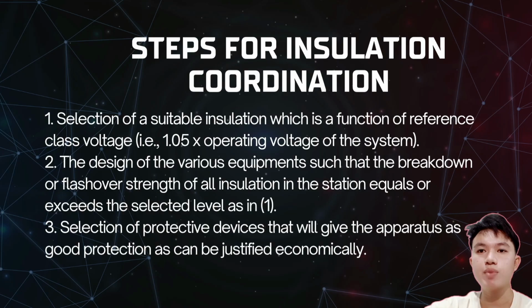So the first step is picking insulation based on the reference class voltage. This is usually calculated as 1.05 times operating voltage of the system. This slight increase provides a safety margin for normal fluctuation in the grid. So second step, the design of the various equipments such that the breakdown or flashover strength of all insulation in the station equal or exceed the selected level as in 1. All equipment in the station must be built so its breakdown strength, the point where the insulation fails, is equal to or higher than the level selected in step 1. Essentially, every component must meet a minimum toughness requirement.